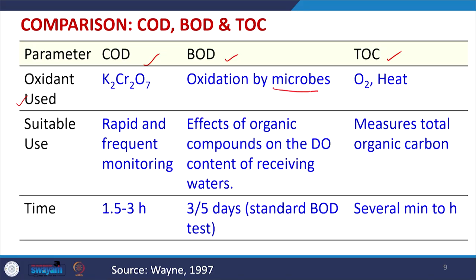In terms of oxidants used: COD uses a highly oxidizing chemical — potassium dichromate; BOD oxidation is carried out by microorganisms; and the TOC analyzer uses oxygen or heat for oxidation. COD analysis is rapid, taking around 1.5 to 3 hours. The standard BOD test requires 3 or 5 days and measures the effect of organic compounds on the dissolved oxygen content of the receiving water. TOC measurement takes only several minutes up to a maximum of 1 hour using instruments.